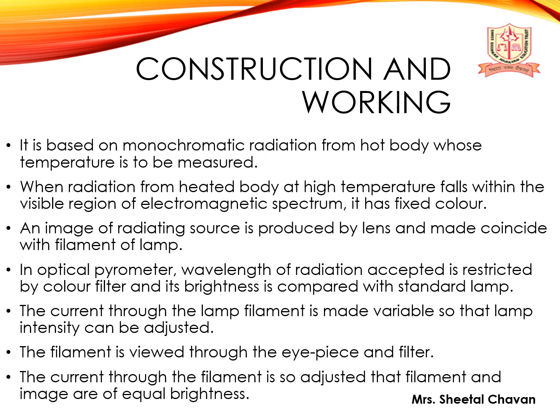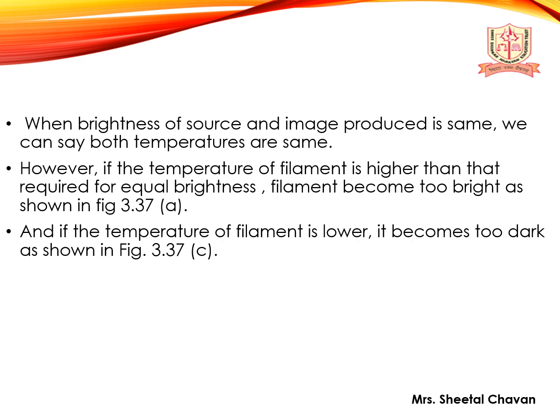The filament is viewed through the eyepiece and the filter. The current through the filament is adjusted so that the filament and the image are of equal brightness. When the brightness of the source and the image produced is the same, we can say both temperatures are the same. However, if the temperature of the filament is higher than required for equal brightness, the filament becomes too bright, as shown in figure 3.37a. And if the temperature of the filament is lower, it becomes too dark, as shown in figure 3.37c.